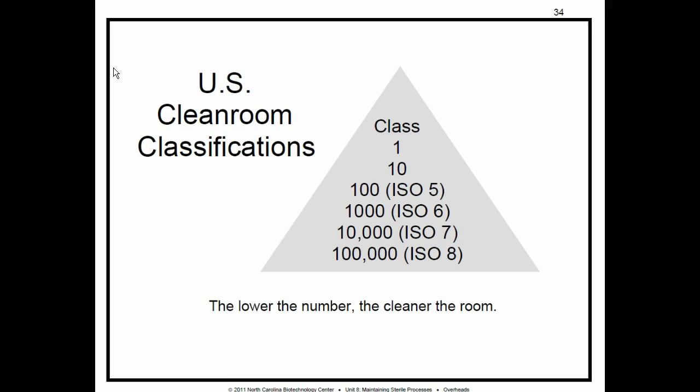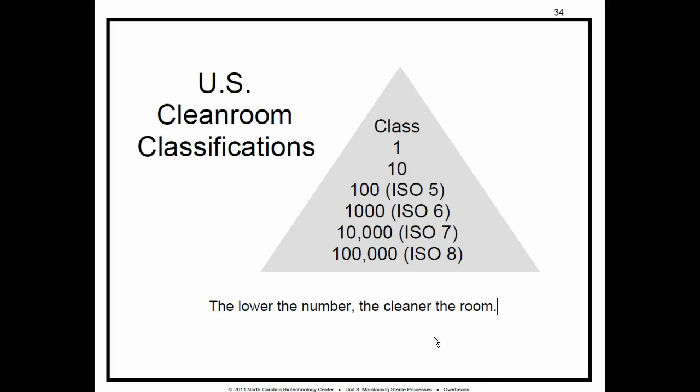In the older U.S. system, which we will use on this test, a Class 100 means it will allow 100 particles — not 101; 99 is okay, but 100 is the maximum number of particles of 0.5 micrometers or larger per cubic foot of air. The newer U.S. standard and international ISO system are also listed in your book. Very important: the lower the number, the cleaner the room. Please know that for your test.